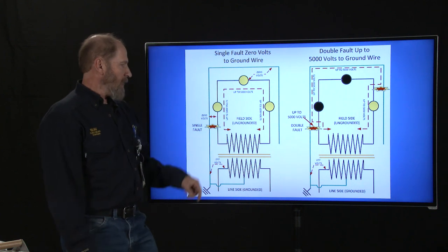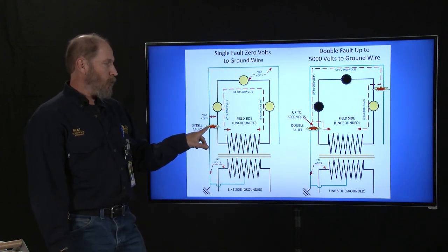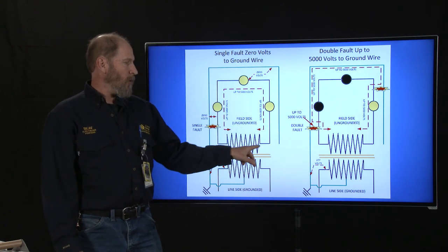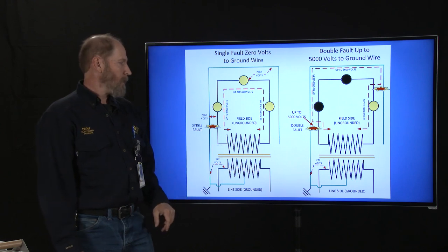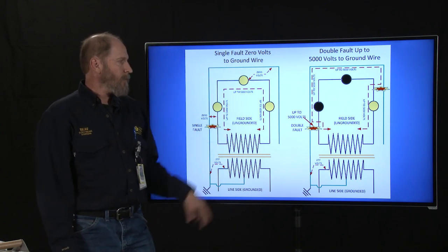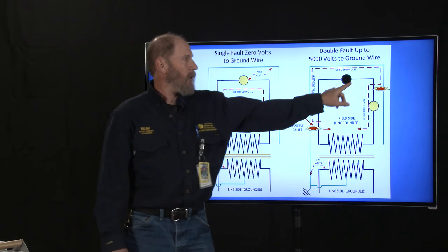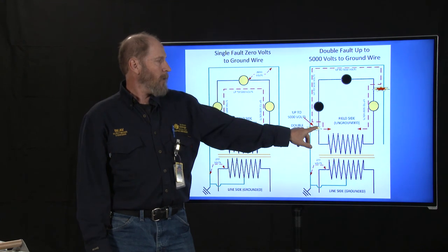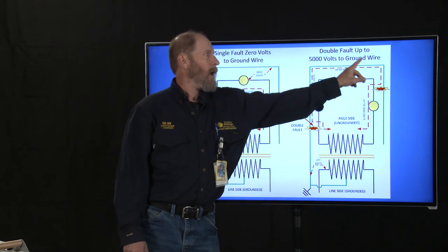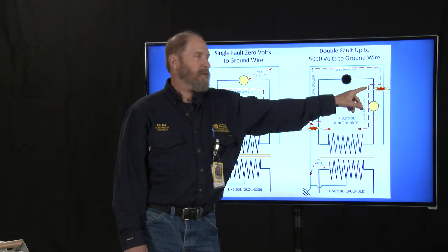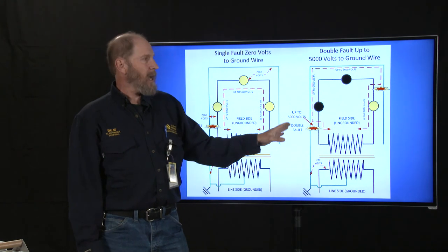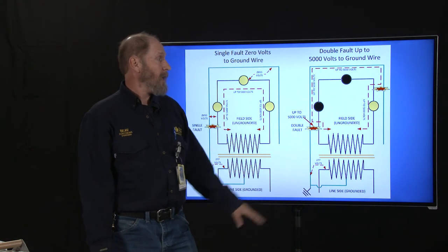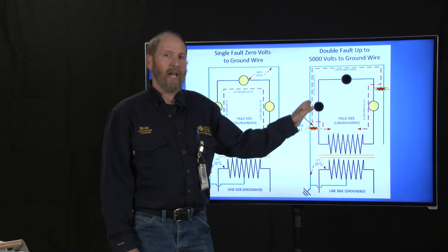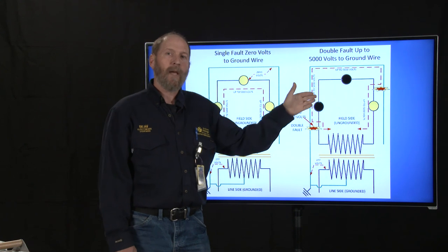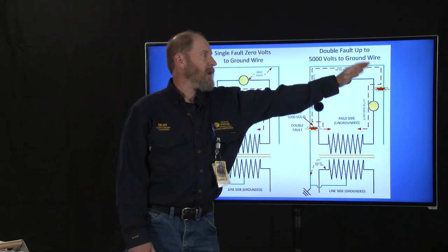But what happens if we have two faults out there? In this situation, we have a single fault, and the electricity could go to ground, but it won't get it any closer to this side of the transformer where it wants to go. So it's like a dead-end street. It won't go down that way. But if we have two faults somewhere in the system out there, it will jump out onto the ground wire and use the ground wire as a path to get back into our system at a different point. The reason it'll do that is because electricity follows the path of least resistance. There is more resistance in our wiring, which has lighting in it, than there is on the ground wire or the pipe that's in the ground or the water in the ground. And so it will use that instead of our lights.